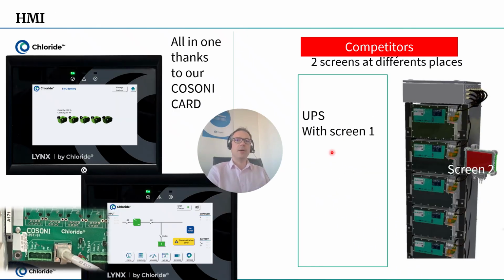Second point: you will see on the market some UPS with a screen or LCD or small HMI inside the UPS, and a second HMI beside the rack, the battery rack. So you end up with two different screens at different places. The decision we made at Chloride was to create one HMI for the UPS where you can check everything about the rectifier. If you press this button, battery sodium or SMC battery, it opens a window to check everything about the battery.